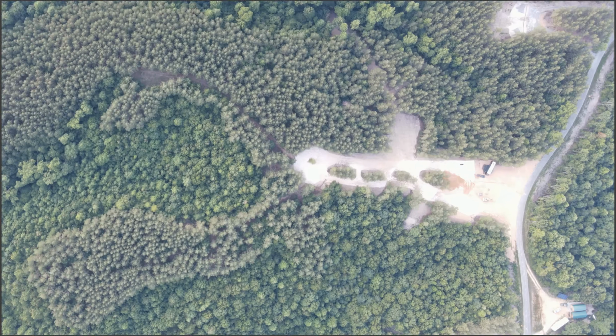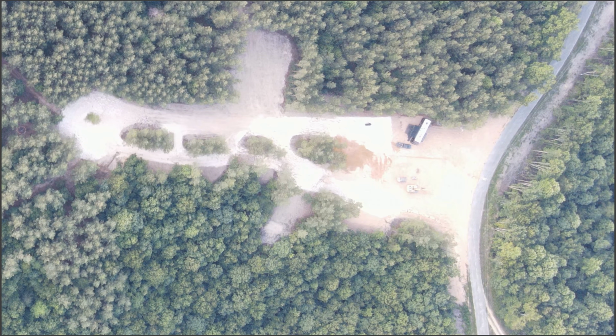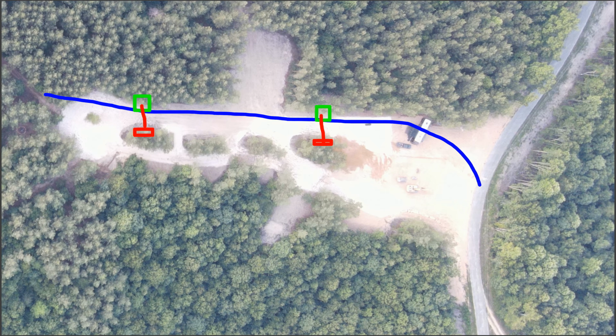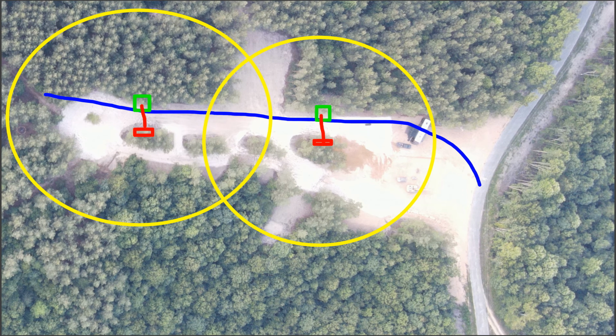Now, the general rule of thumb I've heard, and you should do your own due diligence, is after you come out of a transformer you don't want to go more than 300 feet. So to cross the road here where our transformers are is approximately 30 feet, so from our power panel we want to try to reach everything within 270 feet. This front area is 500 feet.